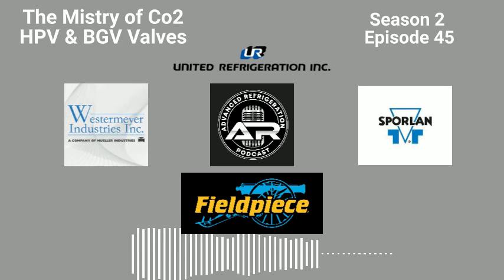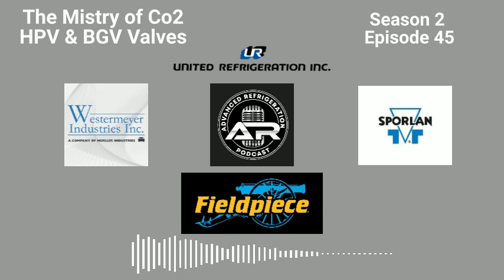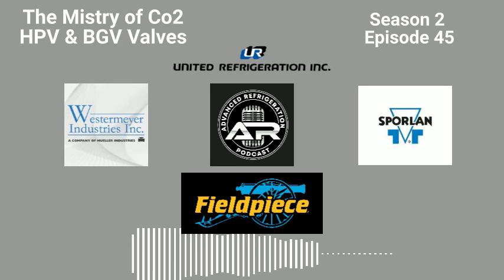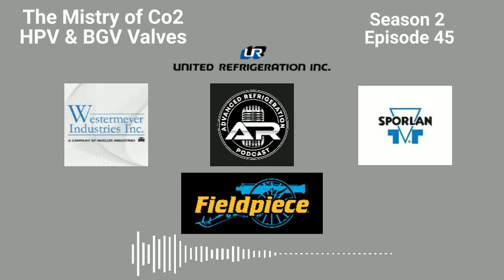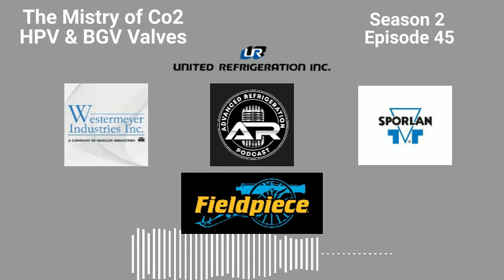So if there's a power failure or something like that, that valve's going to instantly close on its own because that pressure is going to start to creep up a little bit, and it's going to instantly shut the high pressure valve. It's going to do what it needs to do, and it's going to shut the flash gas bypass valve once it realizes that it's not doing anything. So it realizes it's in an emergency situation.